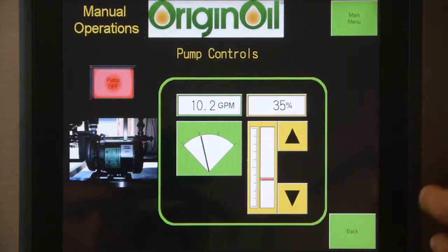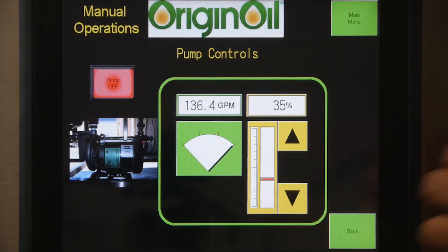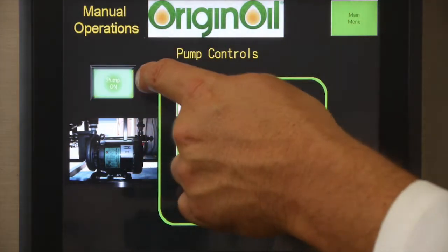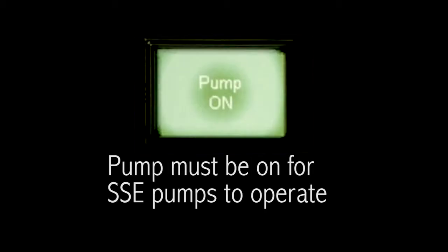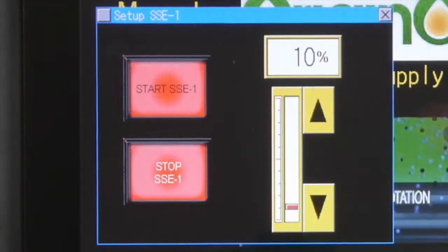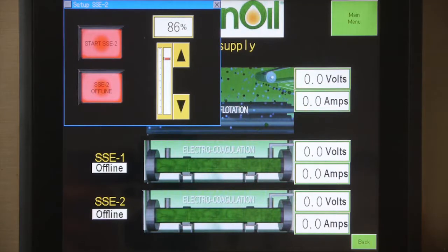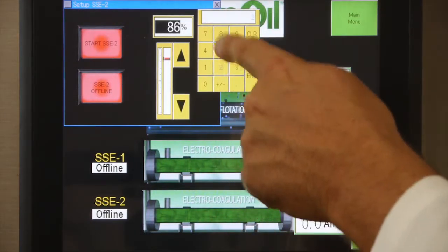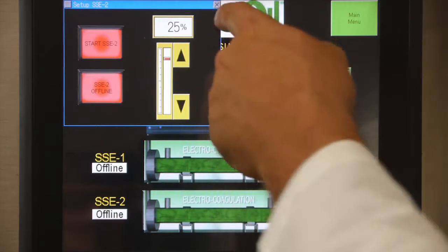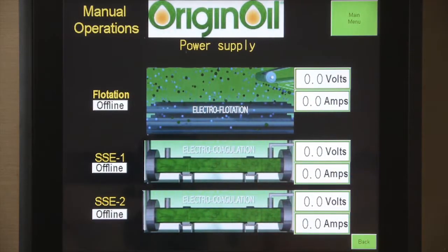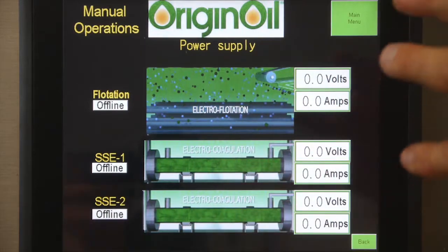The reason it went to this warning window is because the pump is not on. The pump has to be on in order for the SSEs to turn on. Once the pump is on at a set percentage, the SSE will engage. The bottom line is that when you have flow, you can have current into the SSEs. If you don't have flow, you don't want current in the SSEs.